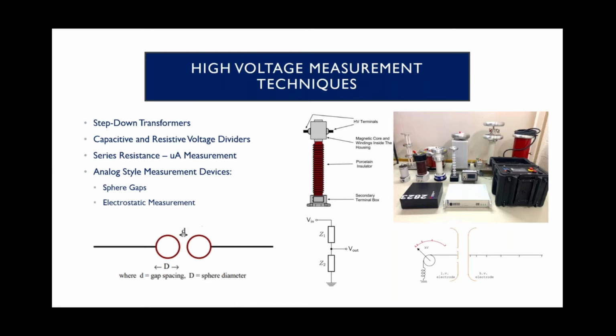Then you also have the technique of using a series resistance. This uses a very specialized high voltage resistor, typically multiple in series to keep the loading and the voltage per resistor down. In series to essentially convert the voltage to a very low current, which can then be measured with a precision ammeter.